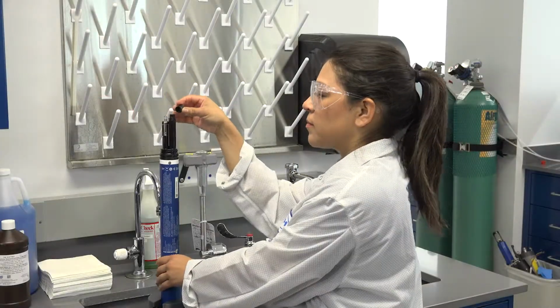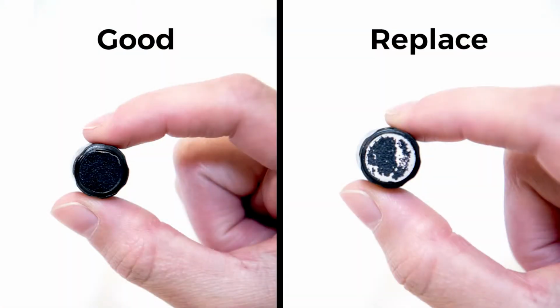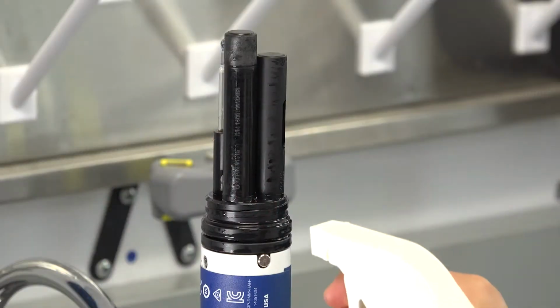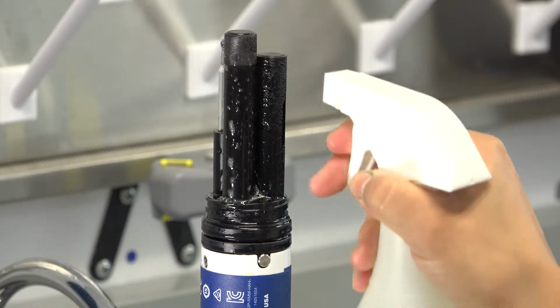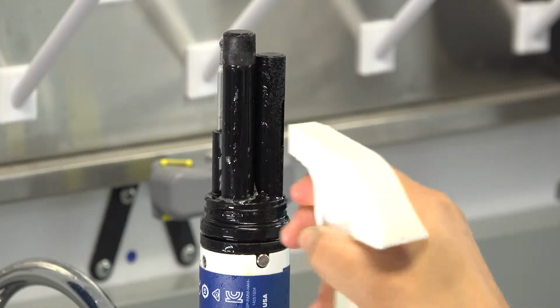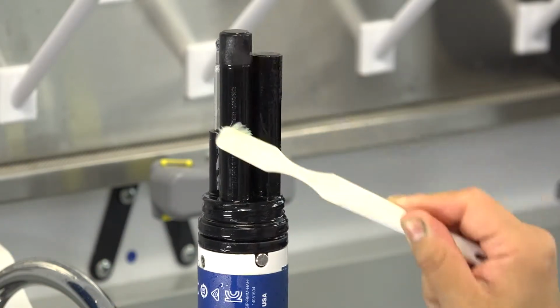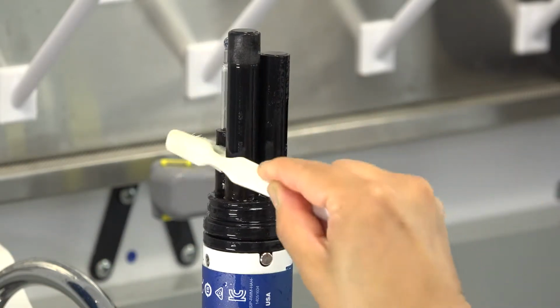Hard scrubbing will remove the black coating from the outside of the sensor cap. If any of the coating is missing or removed, the cap must be replaced. If deposits on the sensor are difficult to remove, soak the sensor in warm, fresh water until the deposits soften. Never use organic solvents such as acetone or methanol on any part of the sensor or cap. When the sensors are clean, the LDO is ready to calibrate.